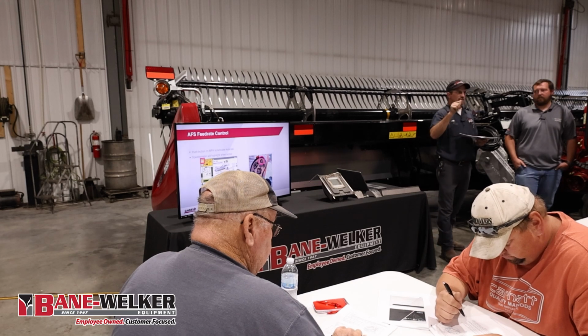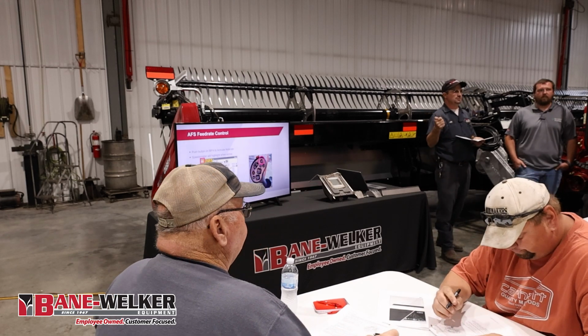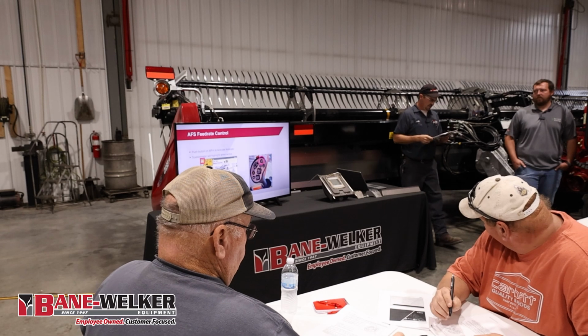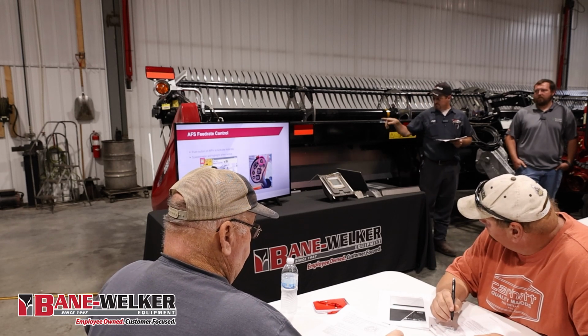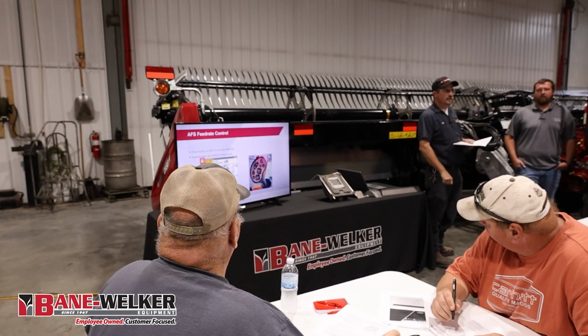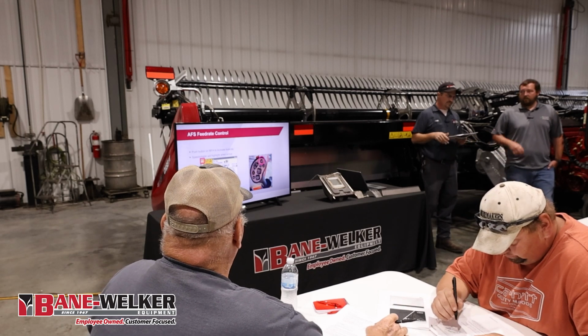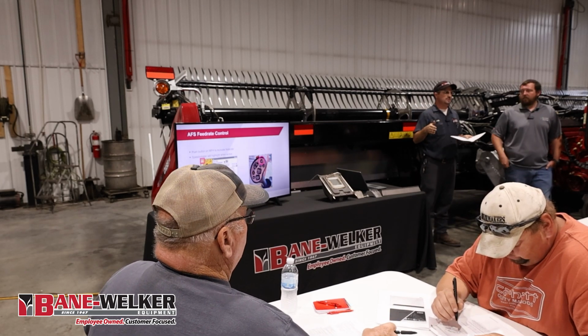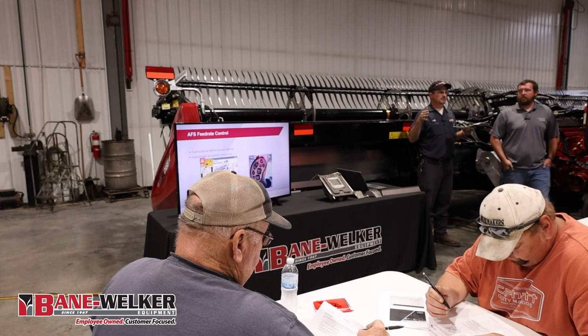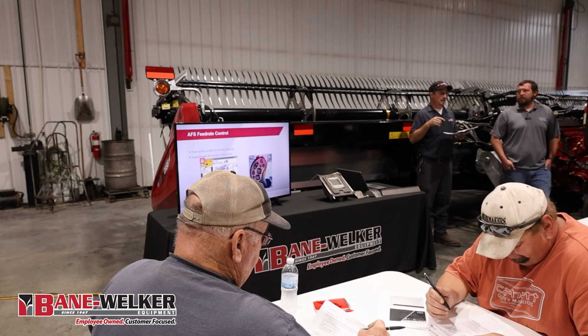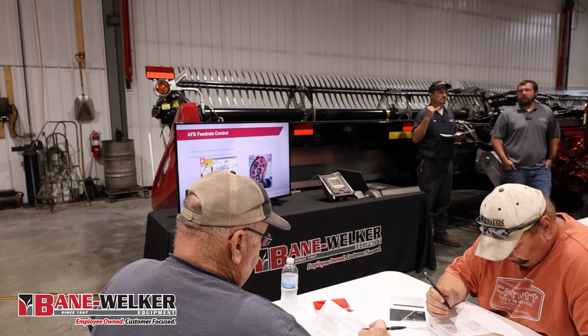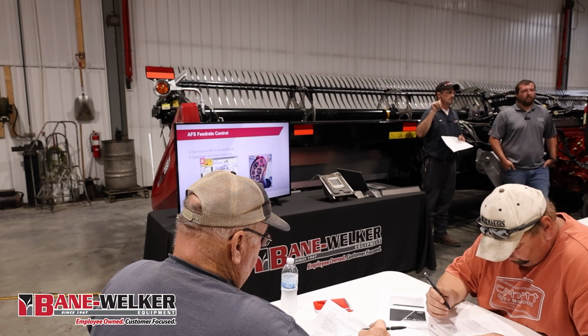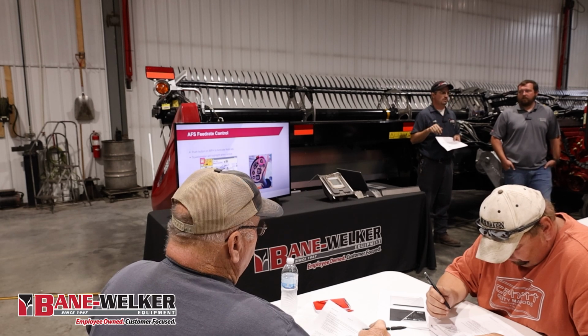You're going to press and hold that feed rate button on your multifunction handle for 2 seconds. Then an hourglass is going to pop up by that indicator for feed rate, and it's going to be doing your calibration at that moment. It's basically telling it this is where I want you to run. That's very critical, especially on that fixed throughput - that's how you're telling it what your throughput is at that moment.